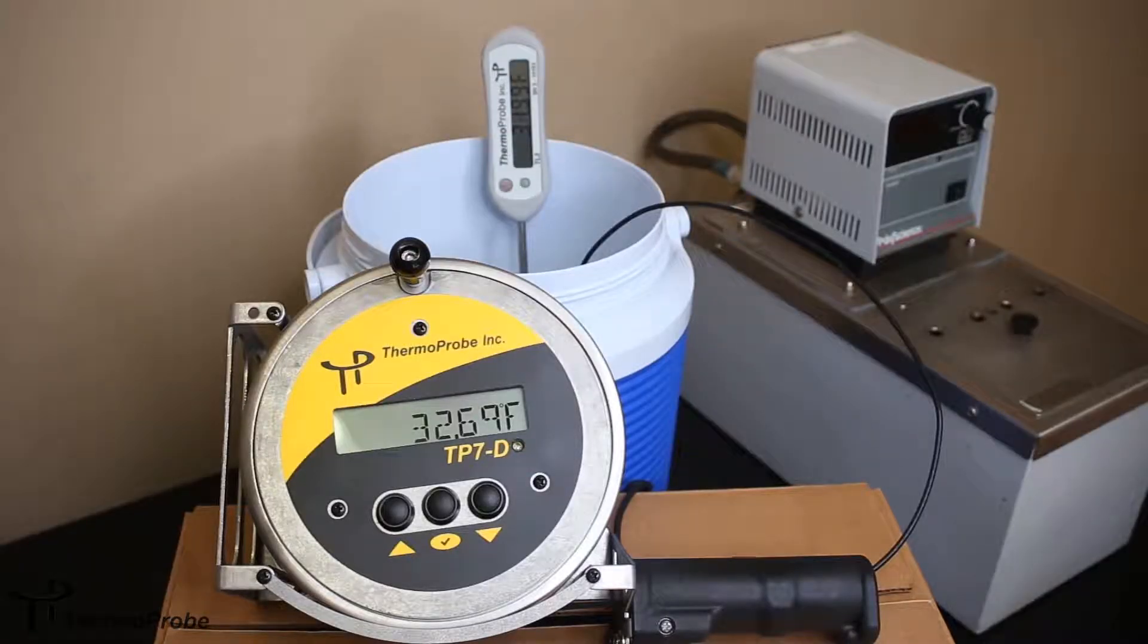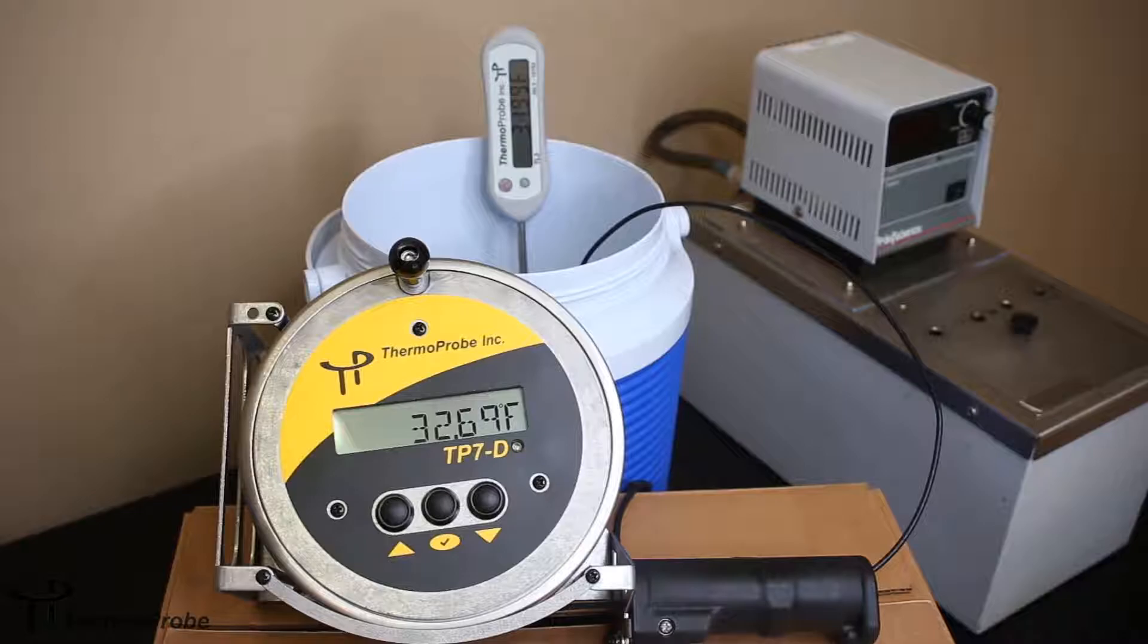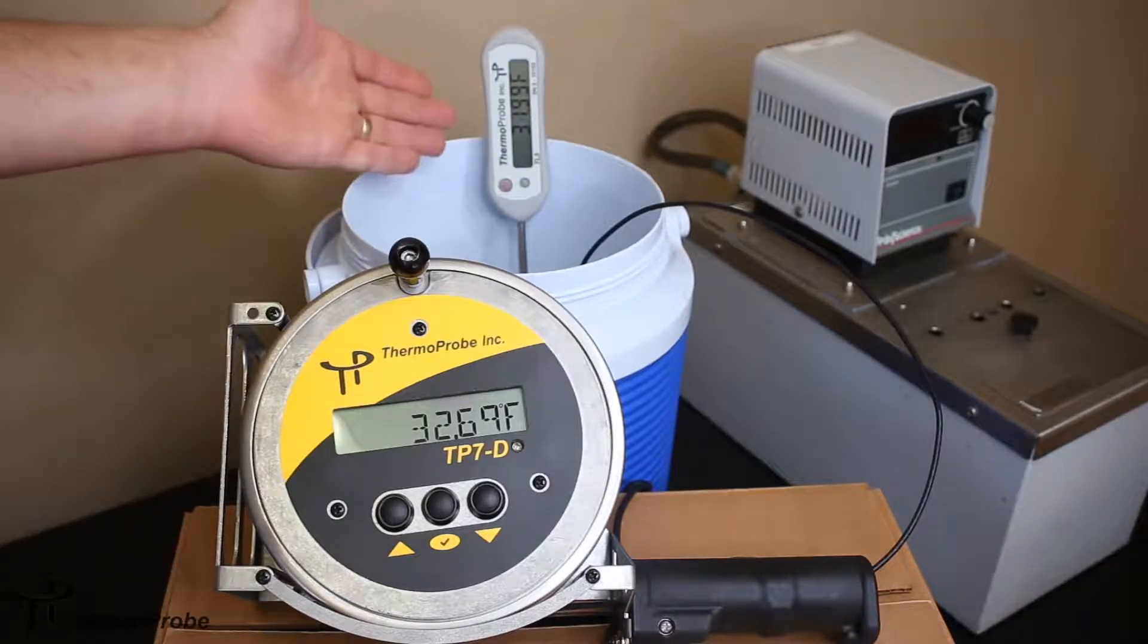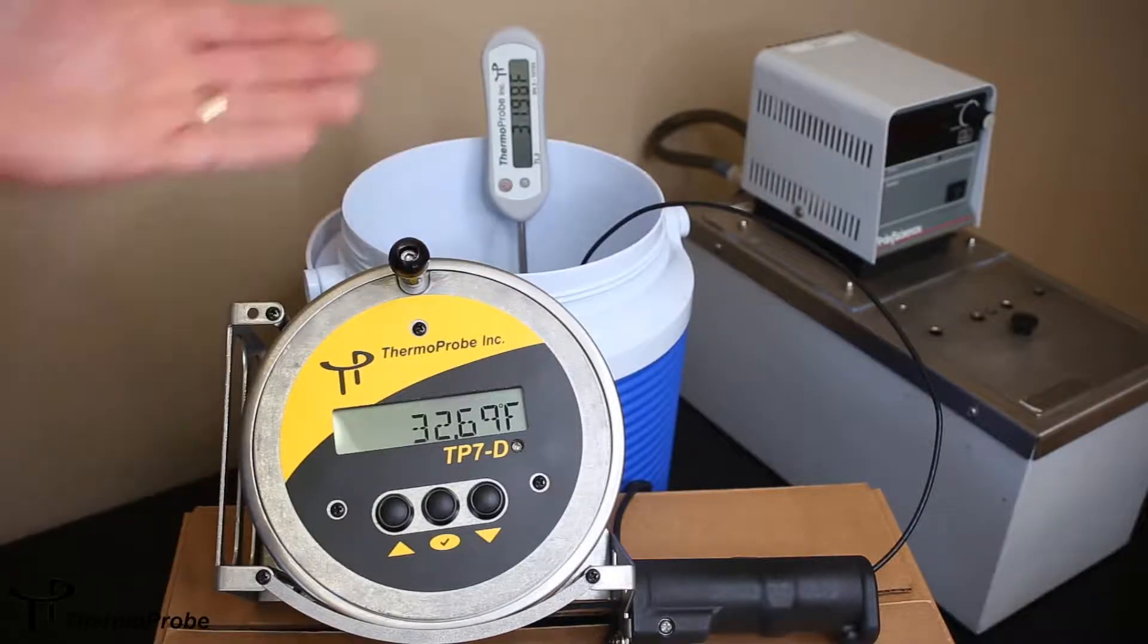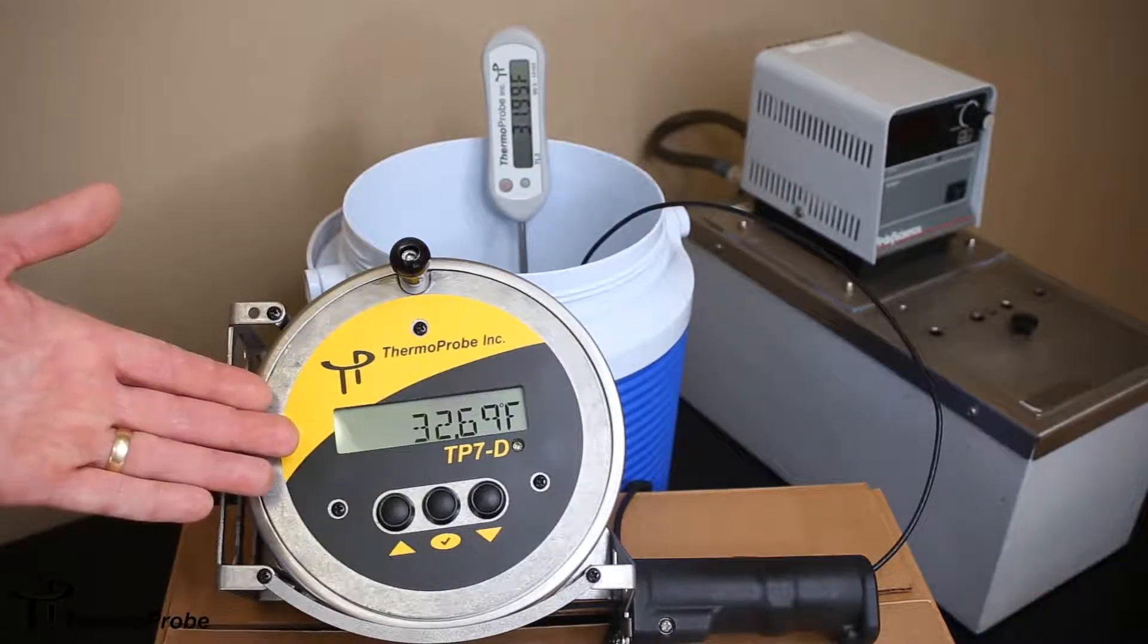This is an illustration of how to do a calibration adjustment to a TP7D or a TP9A. The equipment needed in this case will be an ice bath, a calibrated reference, and this is a TL3, obviously the gauging thermometer that needs to be adjusted.